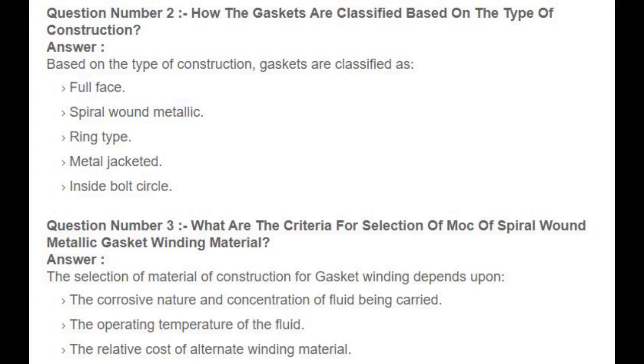Question number 3: What are the criteria for selection of material of spiral wound metallic gasket winding material? Answer: The selection of material of construction for gasket winding depends upon the corrosive nature and concentration of fluid being carried, the operating temperature of the fluid, and the relative cost of alternate winding material.